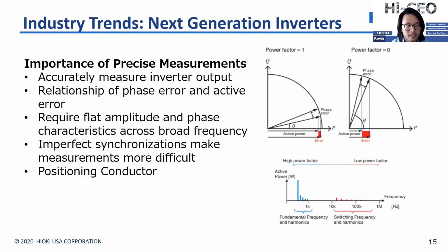Also, when we're taking these measurements, it's important that we position the conductors at the center of our sensors, since all current sensors are susceptible to the effects of the position. So keep in mind, the sensor's measurement accuracy is always defined at the center position of the sensor. So when we're measuring at these high frequencies, it's important for us to keep those in the center for high precision and more reproducible measurements.